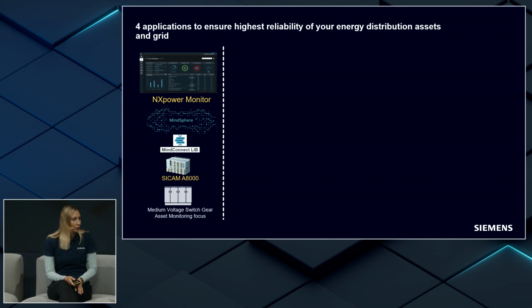We also provide energy monitoring, documentation, what should be in place, because remember the remaining lifetime of a switchgear is up to 30 years. That's quite an age. Right, maybe you have lost the documentation, that's a lot of documents, and then maybe you move offices and say, come on, that's old stuff. Correct, but it's important to have it. Then you stand in front of the switchgear and the documentation is missing. So that's the first application.